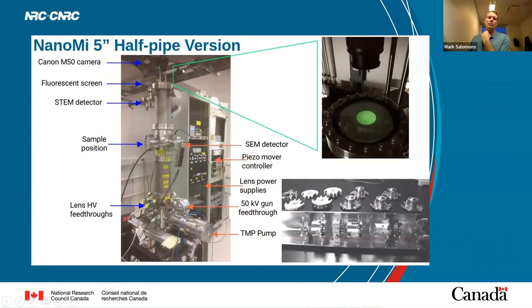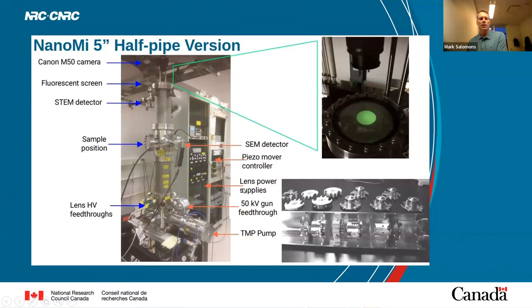For detection, we use a standard off-the-shelf camera with a phosphorescent screen. We built our own STEM detector, and for an SEM detector you can build your own — we put in an Everhart-Thornley detector that we had off the shelf, but those are fairly simple to build. We build all our own electronics here: piezo movers, lens power supplies — currently commercial but all can be built. We use a turbomolecular pump for vacuum, baking the system, and shooting for about 10 to the minus 10 Torr, with standard off-the-shelf high voltage feedthroughs.